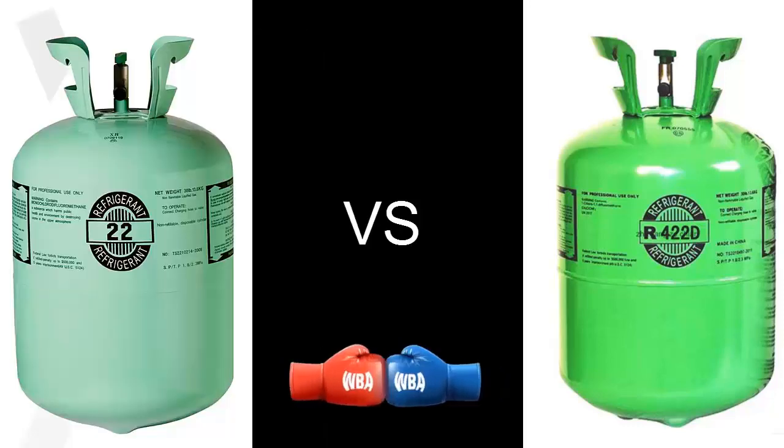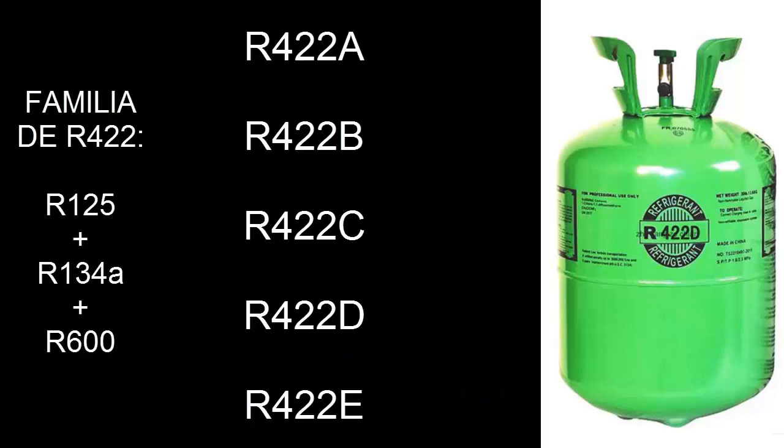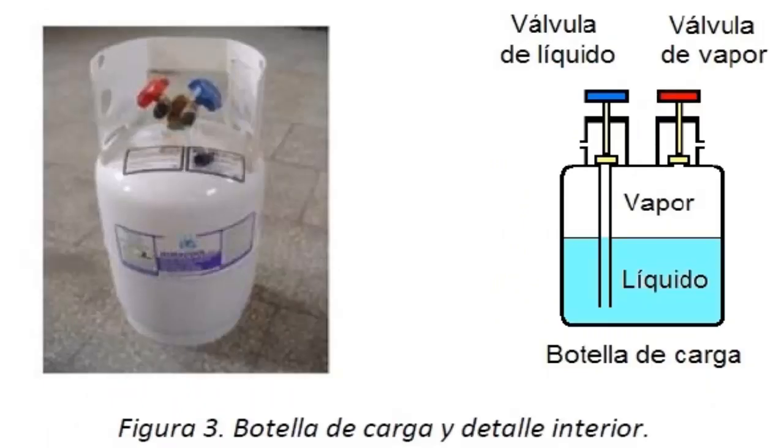Although the gases in the R422 family have the same components, they vary in their proportion percentages. It's important to note that R22 can be charged either in liquid or gaseous phase, while the gases in the R422 family must be charged only in liquid phase.